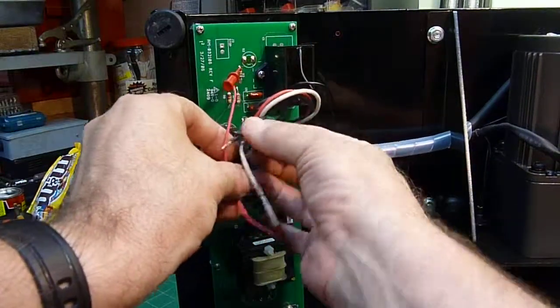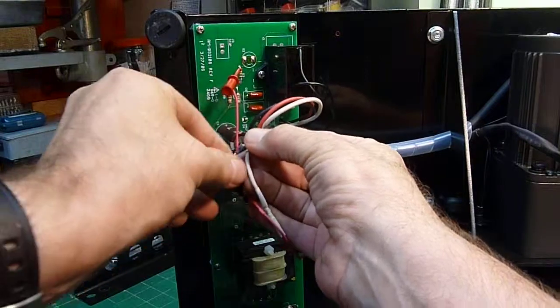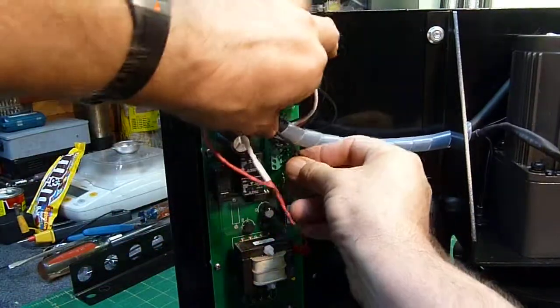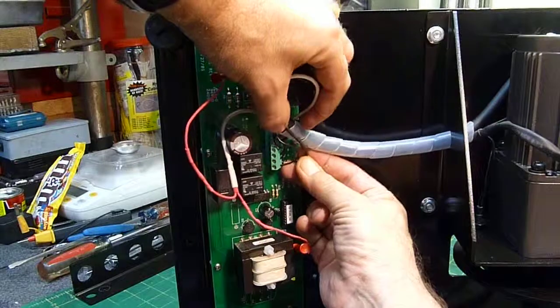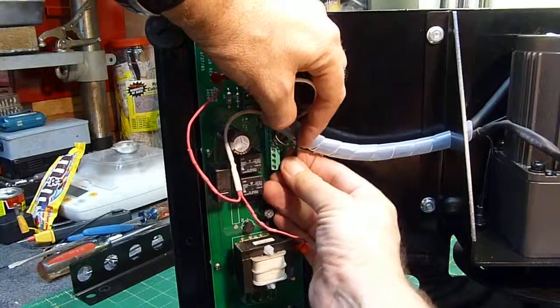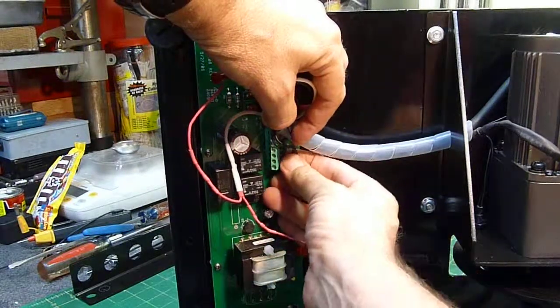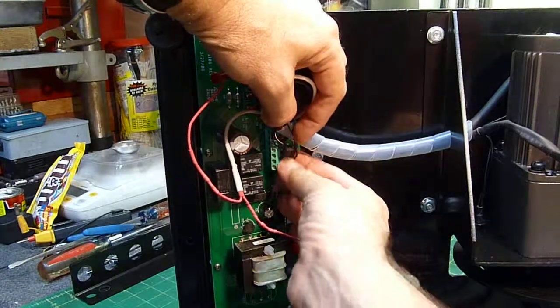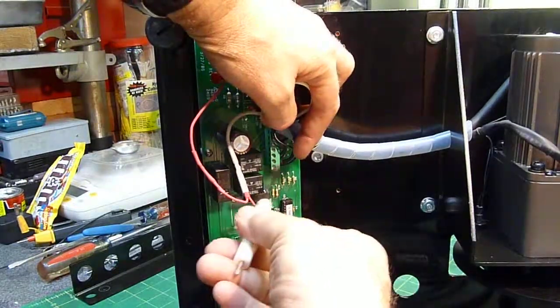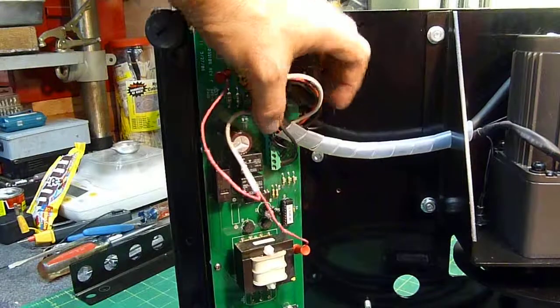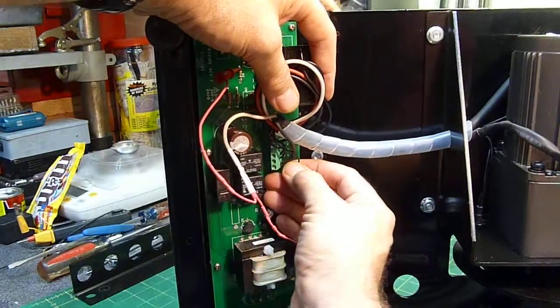And then you take the black wire of the SmokeMate test set, which should already be pre-tinned so it doesn't fray. And you want to get it right up in there like that in the same hole. Try to get the two wires side by side because the clamp has a bar that clamps down equally across the slot. And you hold those in. And you just tighten the screw up. Good and tight. And the most important part of the installation is make sure these wires are tight.